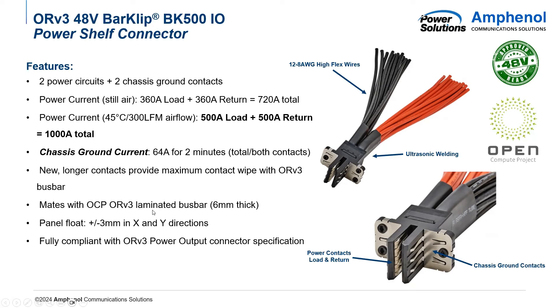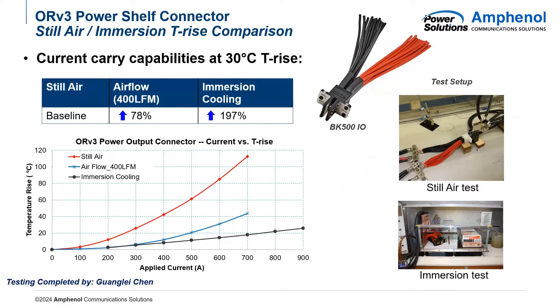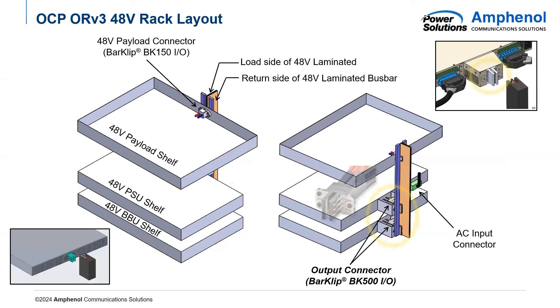The BK500 and the BK150 IO connector both mate with an ORV3 six-millimeter-thick laminated bus bar, meaning that it is power and return. For our immersion cooling tests, this was initial testing that we did, and we were able to achieve almost 200% more current density in an immersion cooling environment when compared to regular still air. As you can see from the chart, still air has a very steep curve as you apply more current to it, and even compared to 400 LFM airflow, immersion cooling is still much more efficient at moving power and not overheating the connector.